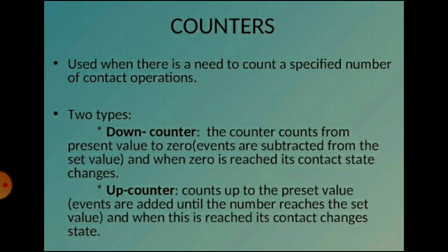So the counter is a component used to count electrical pulses and store the results of the counting procedure. The instantaneous contents can be displayed and or used in a process control algorithm. Counters are classified as up counters, down counters, and up or down counters. An up counter starts at 0 and increments its contents, that means the count total, by 1 in response to each pulse.